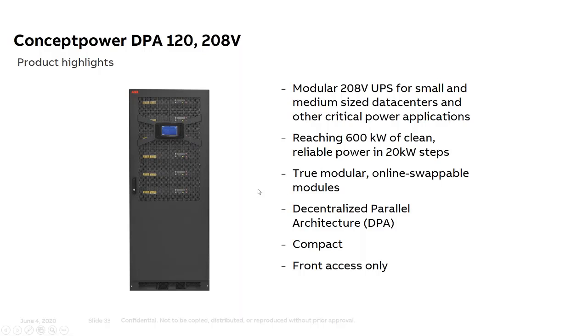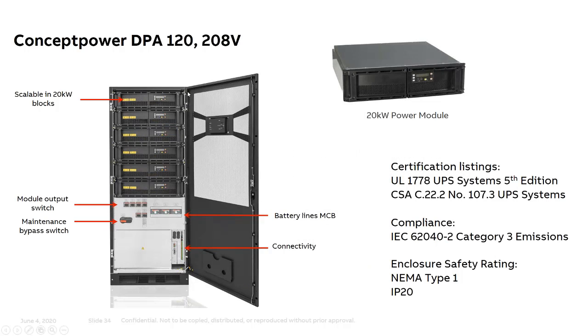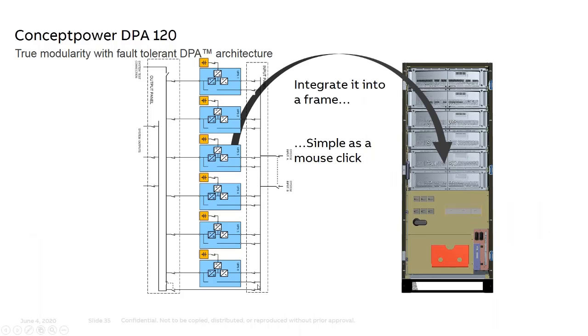And quickly, there's a smaller member of the modular types. There's a 208 volt. We have 2 different frames for this one as well. Very similar to the big brother, the 480 volt. The differences are that it's 208 in and out, 208/120 in and out, and instead of a 100 kW module, it's a 20 kW UPS. 6 of them will fit in there, so it can support up to 120 kW, or you could say 100 kW with N+1 redundancy. That's a very similar drawing. That's what it looks like. It's 6 small UPSs in parallel in one frame, but like the name modular scalable says, the customer can start with whatever they need today, and then they can add more as they need them.